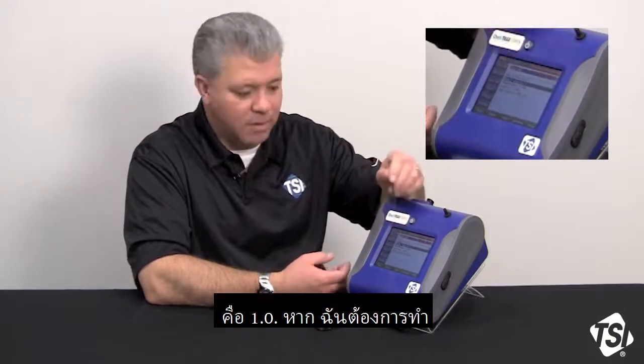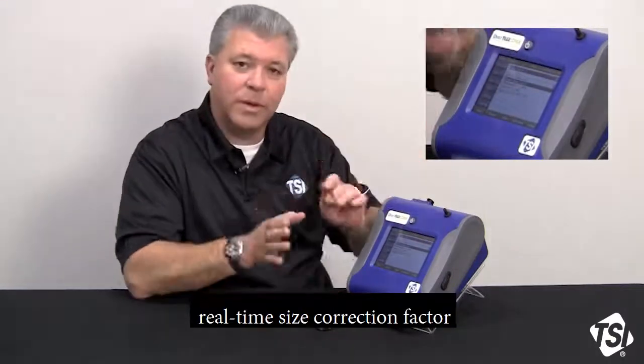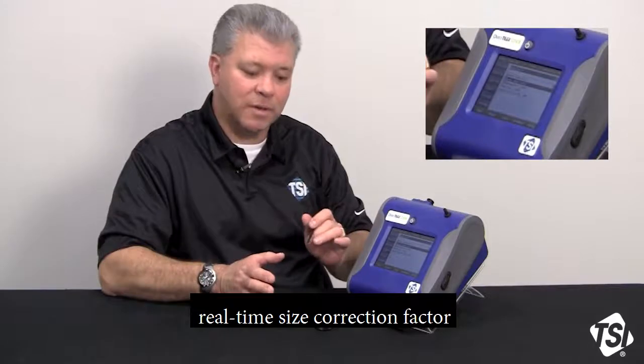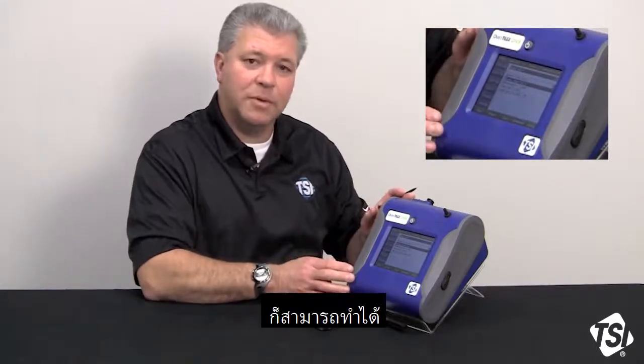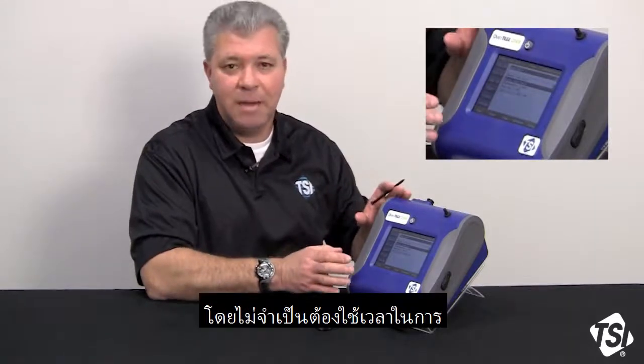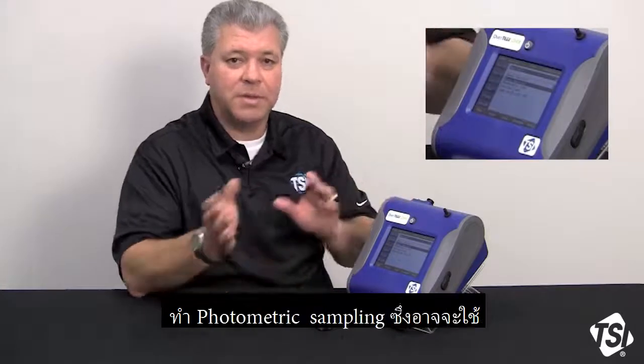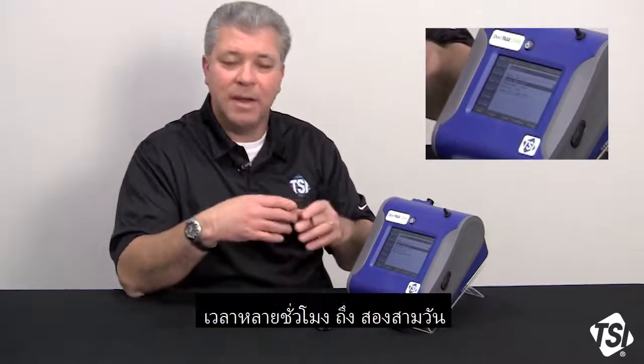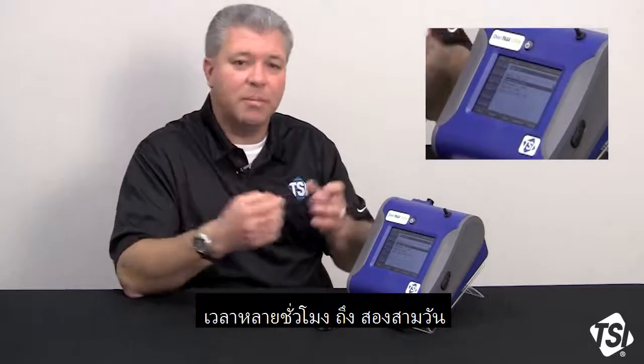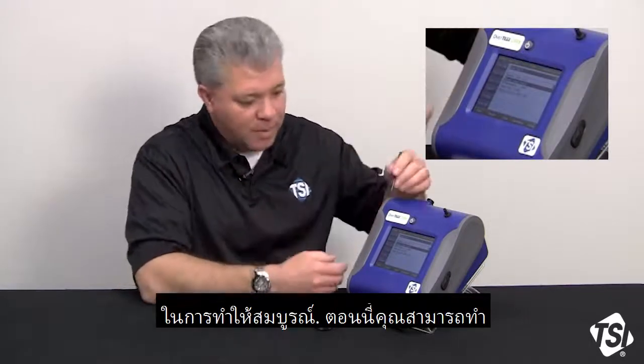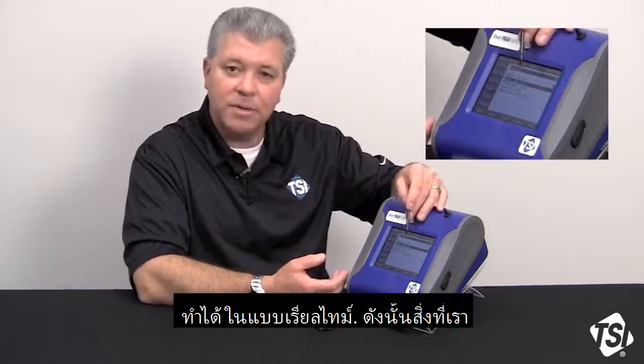It's 1.0. So I want to do a real-time size correction factor. The reason for being able to do that is you don't have to take the time to do all the photometric sampling, which may take several hours to a couple of days to complete enough samples. Now, you can do this in real time.